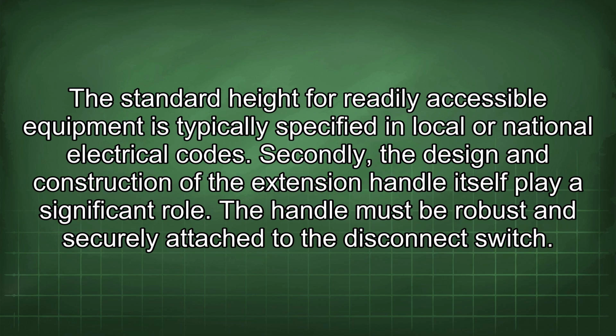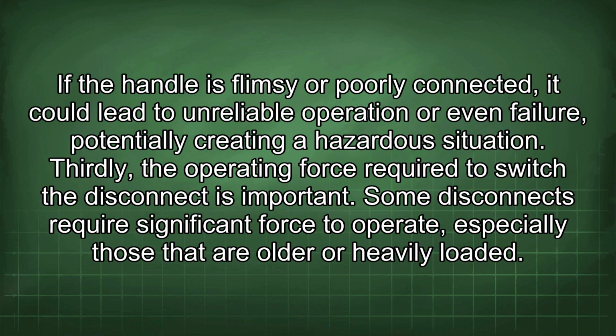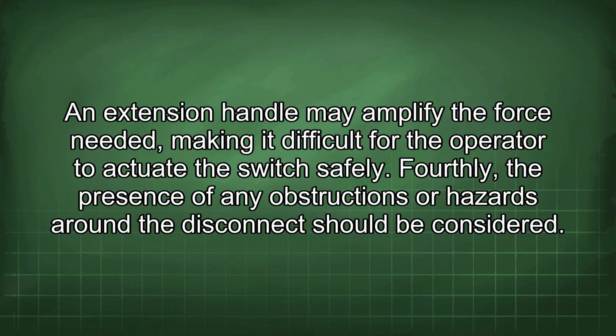Secondly, the design and construction of the extension handle itself play a significant role. The handle must be robust and securely attached to the disconnect switch. If the handle is flimsy or poorly connected, it could lead to unreliable operation or even failure, potentially creating a hazardous situation. Thirdly, the operating force required to switch the disconnect is important. Some disconnects require significant force to operate, especially those that are older or heavily loaded. An extension handle may amplify the force needed, making it difficult for the operator to actuate the switch safely.